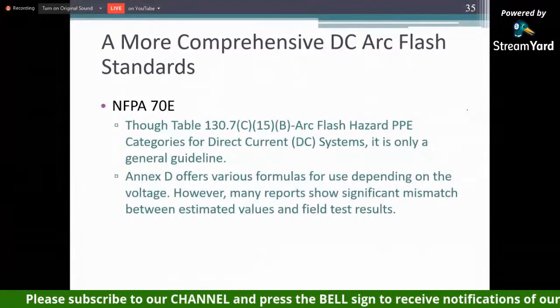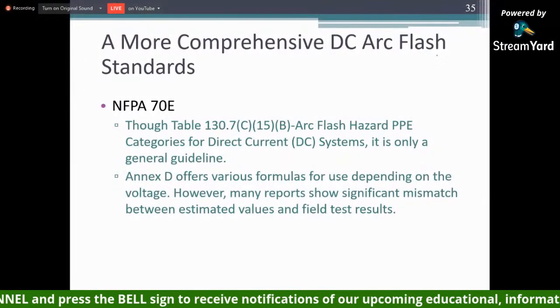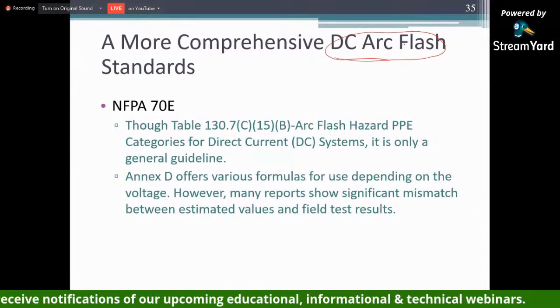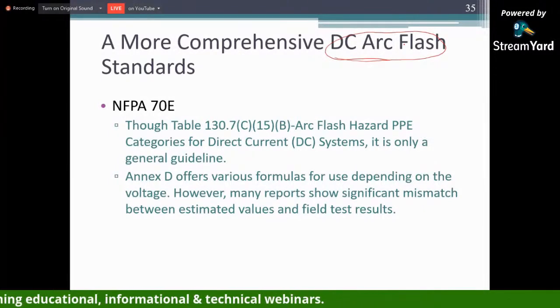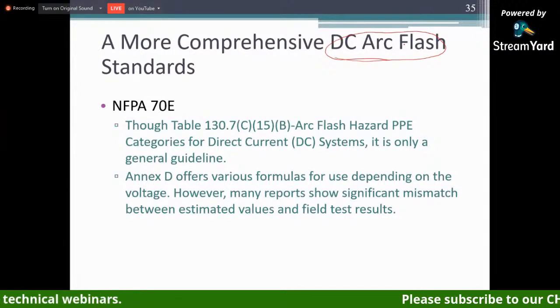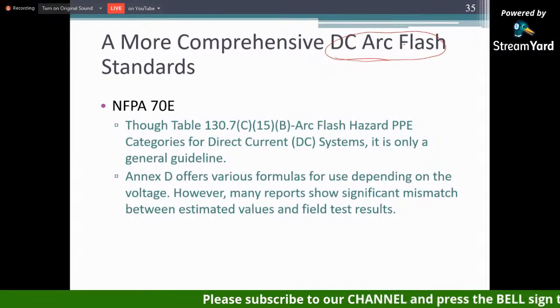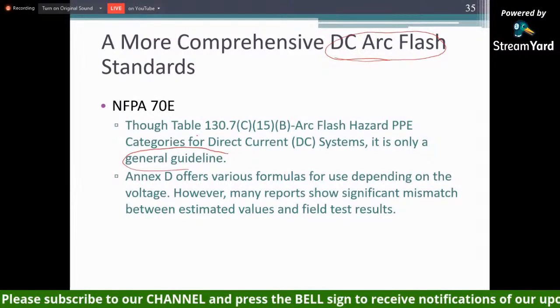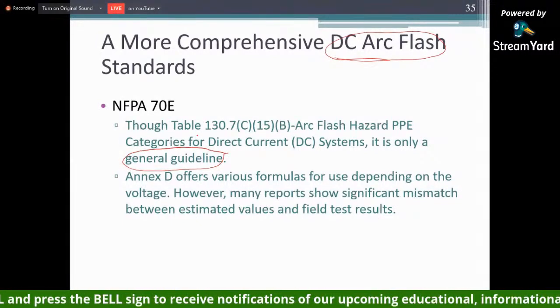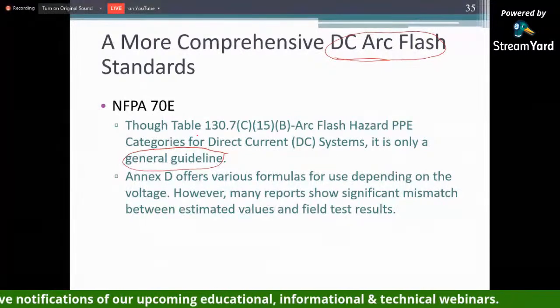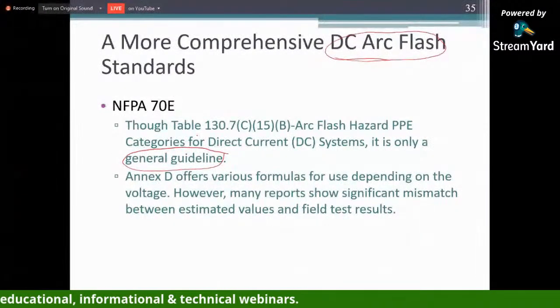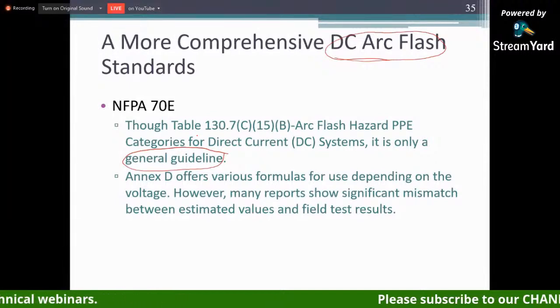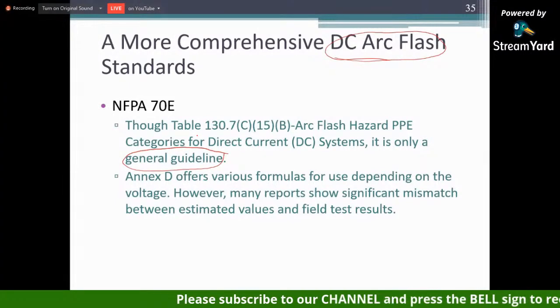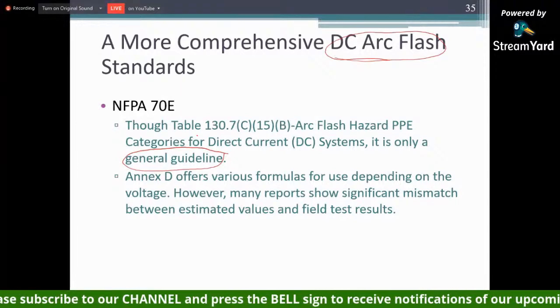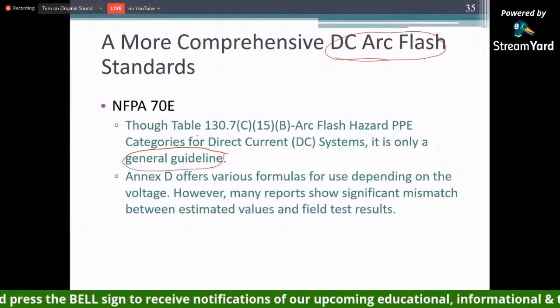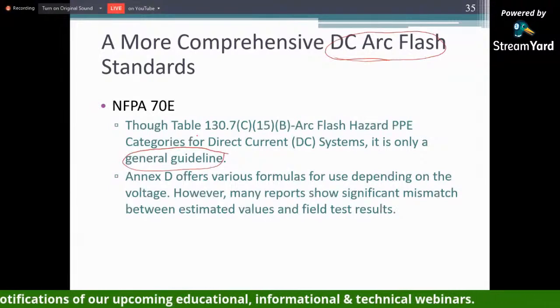Currently I'm working on the DC arc flash part, because in 1584 they are talking about AC. And in NFPA 70E, they do provide some general guideline, but it doesn't really give a very rigid simulation. They provided some formula, but according to a lot of testing and other simulation, the result from 70E is over conservative - it has some mismatch with the test result.